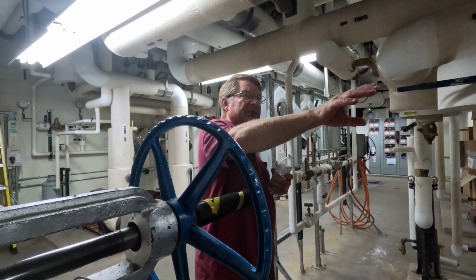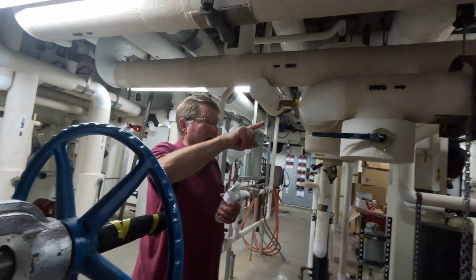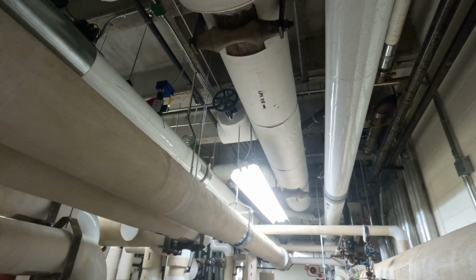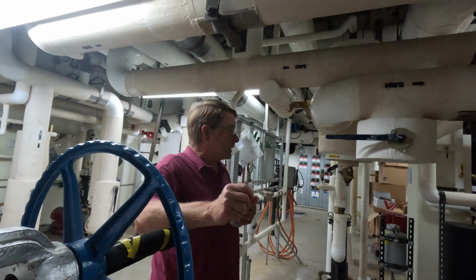This is where the steam comes in. This is the 10-pound steam. So coming from the tunnel that's behind you, the pressure comes in at 175, broken down to 10 pounds for the air handling equipment and for the converters, and then 85 for the glass washers and autoclaves.